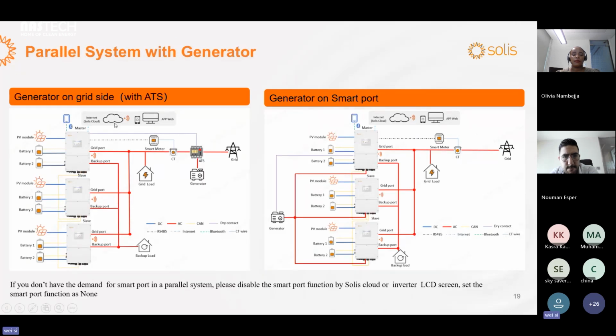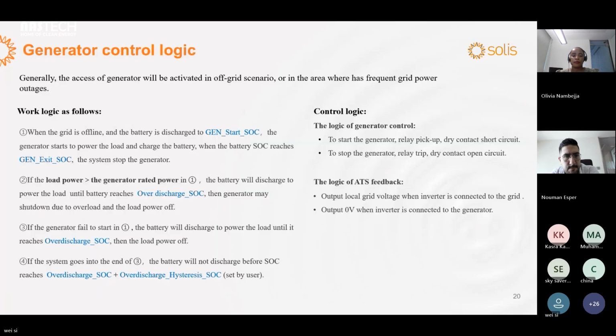About the parallel system with the generator, you can choose these methods, and you can also choose to connect all the smart ports together, then connect the generator with the bigger capacity. It's the working logic of the generator. It will start when the battery discharges to the start SOC and stop when the SOC reaches the exit SOC.